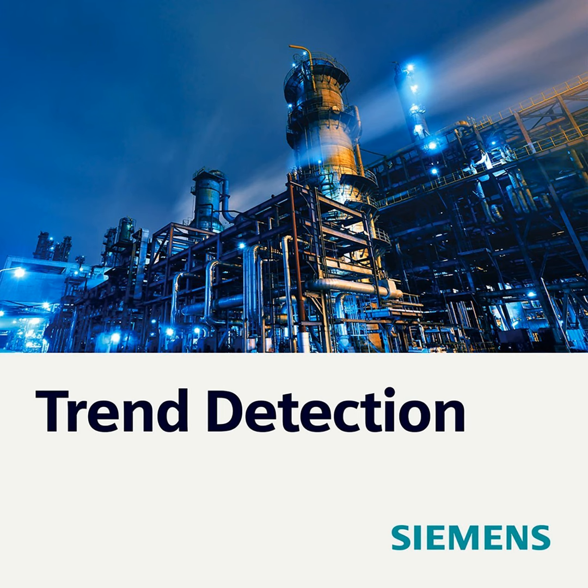Yeah, I think again, you get people in with varied amounts of experience, and people can often overlook the basics. Sensor application, installing the sensor on the proper spot in the machine to get the best frequency response, using the best mounting methodology for the sensors so that you're not dampening the signature. Sometimes even removing the paint between the sensor and the actual machine housing is critical. And so I think those types of things are important.